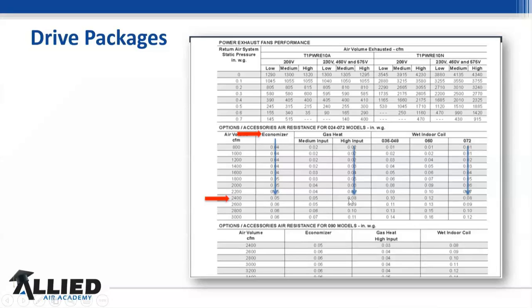So when you get a standard unit, do an emergency replacement, don't forget to include these pressure drops into your static pressure. And then you can see the economizer doesn't have very much, but we still have to account for it. So it's really important that we understand this, and this is where you find out exactly how much a wet coil static drop is going to have.